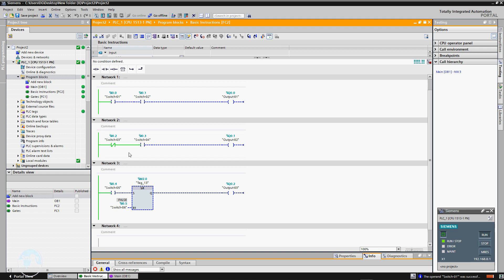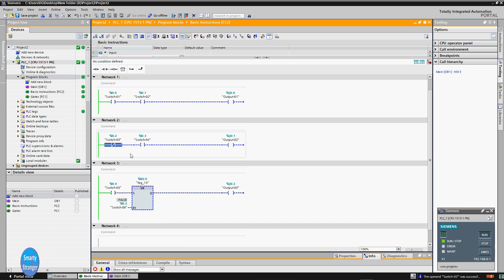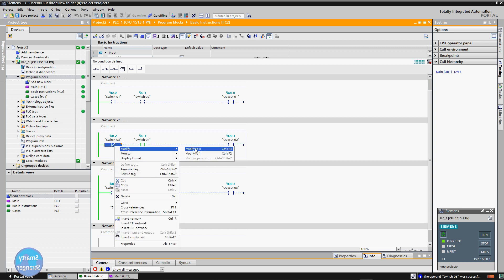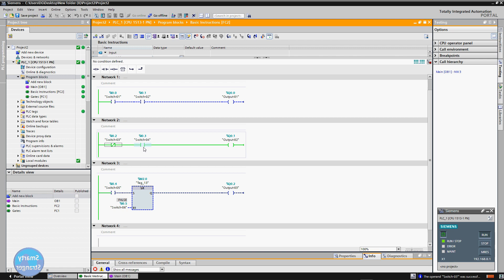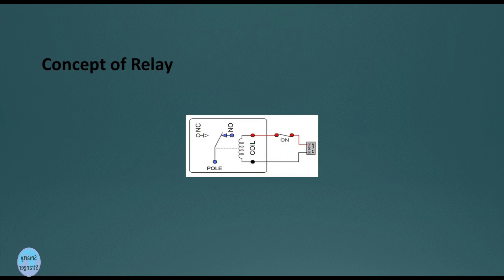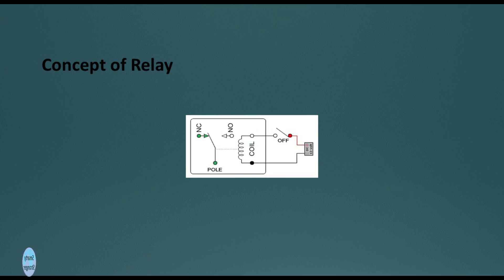In network two, the first button is normally closed and the second is normally open. Since the normally closed contact is the reverse of normally open, it shows high by default. When we press the first button from the field it becomes open, going low. When we press the second button, output Q2 energizes. Then when we press the first button, the output de-energizes. This is how a normally closed contact works — remember the concept of a relay and how its contacts behave before and after energizing the coil.